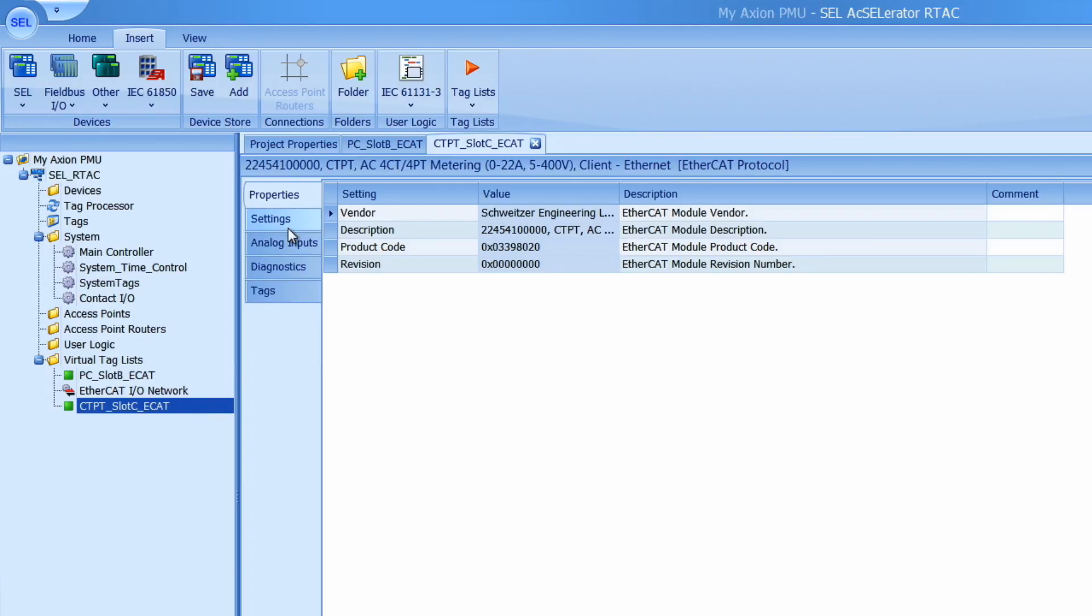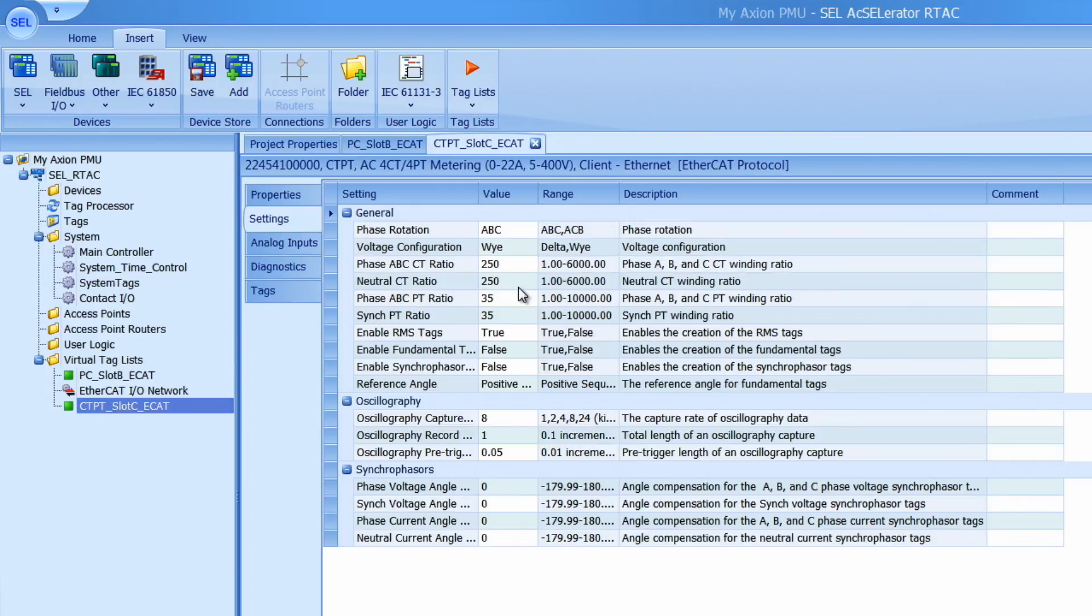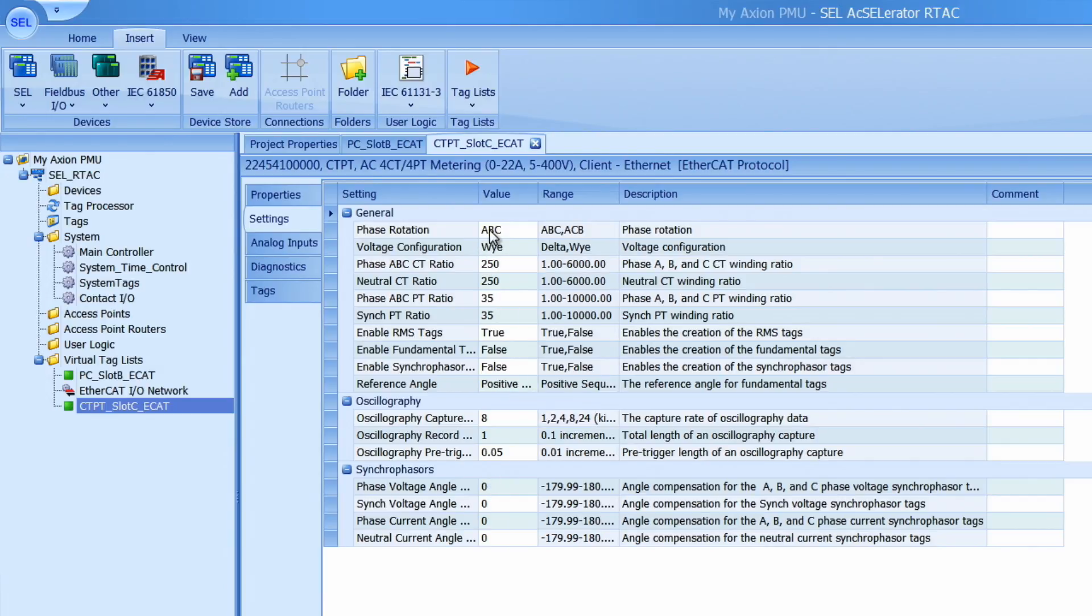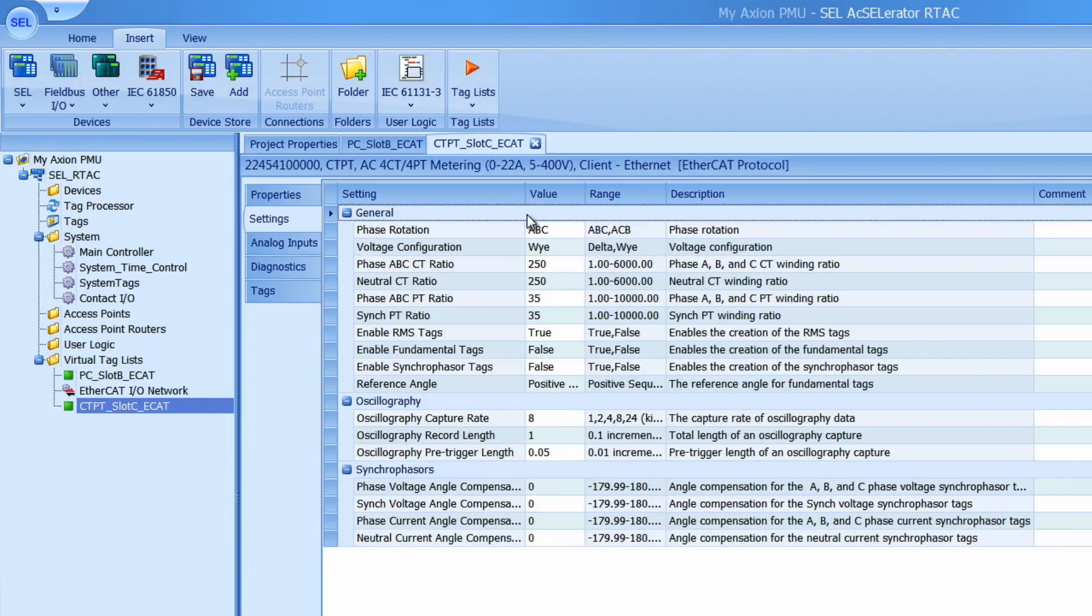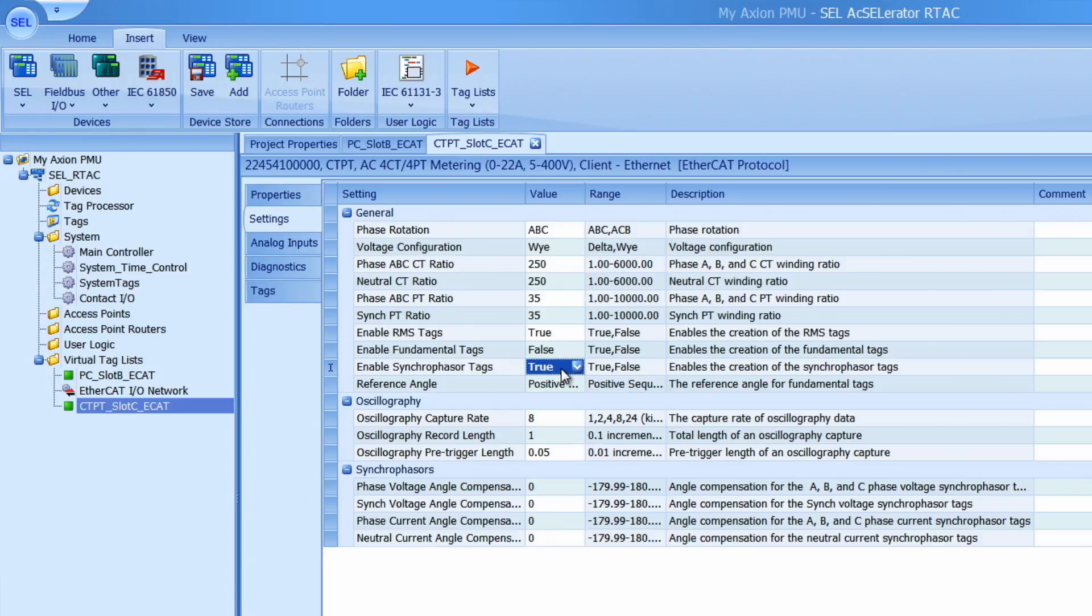So go to the settings tab and you'll notice that there's a few different categories of settings in here. The most important one here to configure is the enable synchrophasor tags. I want to set this one to true by either double clicking on it or clicking on this arrow here to make the synchrophasor tags available in the module.